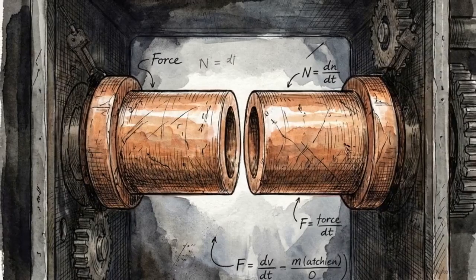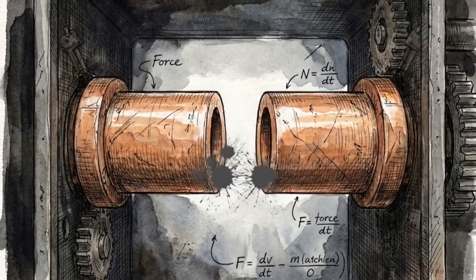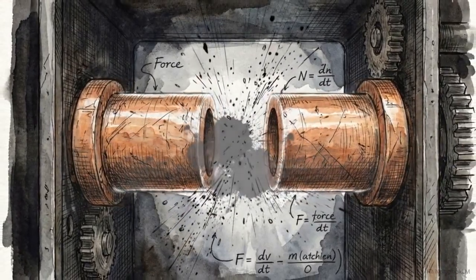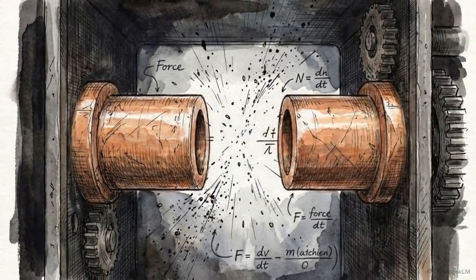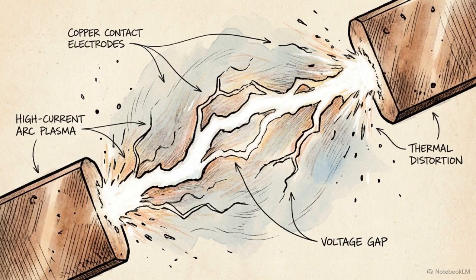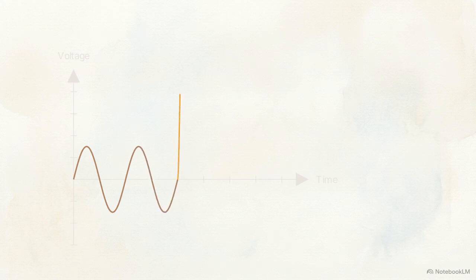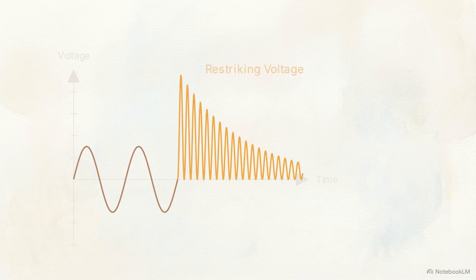The moment the circuit breaker receives that trip signal, it uses extreme mechanical force to violently yank its metal contacts apart. But pulling the metal apart doesn't instantly stop the electricity. The current has so much momentum that it tears through the empty air between the separated pieces, creating a massive white-hot arc. We can see the physics of this struggle on a waveform graph. When the current finally hits zero and tries to stop, a chaotic high-frequency spike erupts across the physical gap. Engineers call this restriking voltage.